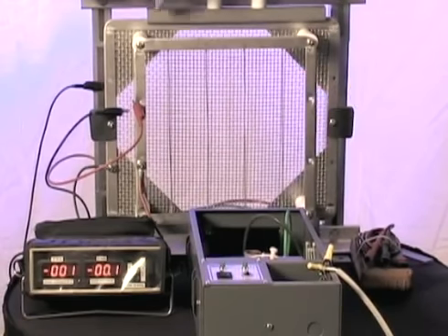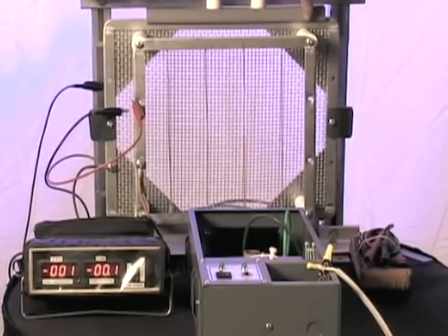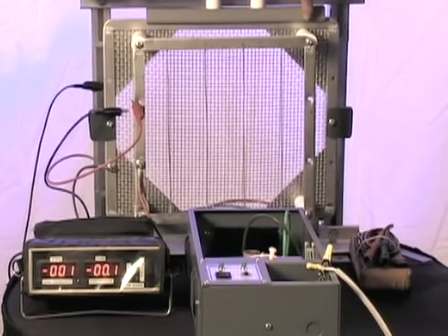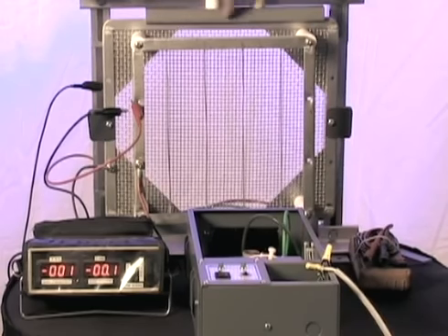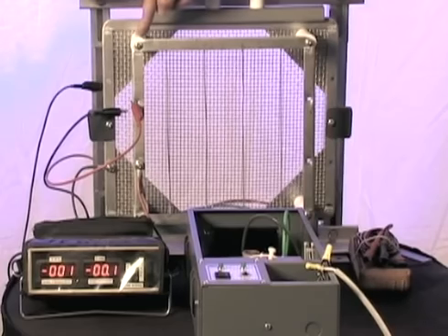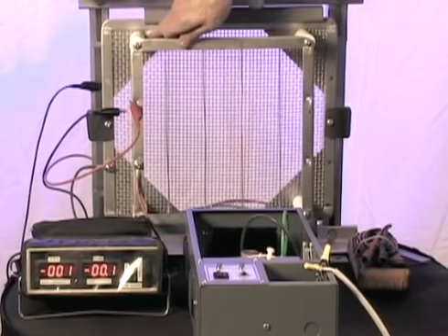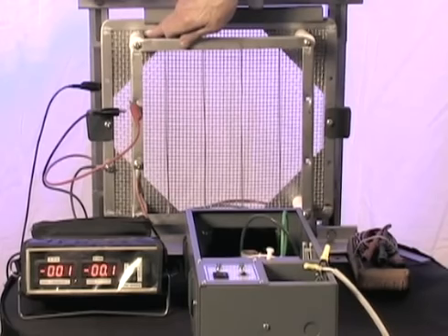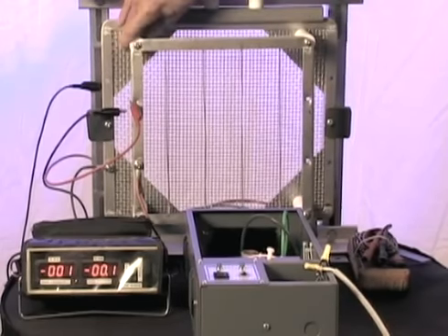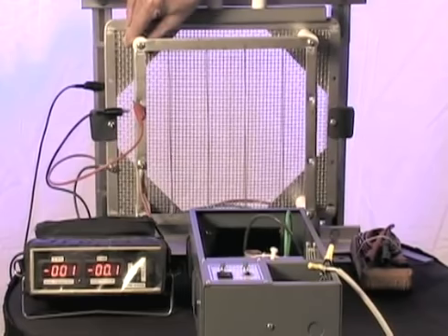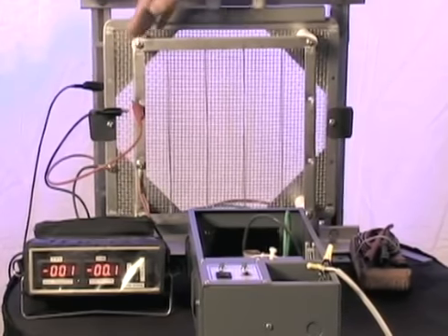Also, the gray PVC track will collect dust and contamination because this contamination exists in the air that goes through the system. So periodically, you will have to clean the gray PVC track and the white Teflon insulators. This will keep your electrodes separate, voltage-wise, and you will eliminate any problems which could be caused by contaminants in these areas.